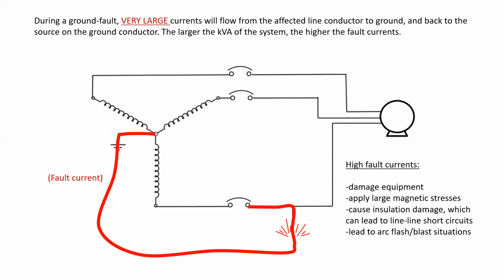And as systems get larger and larger, because we use more and more electricity, we tend to get more extreme situations. So with a solidly grounded system, we can get damaged equipment due to excessive magnetic stresses caused by the huge flow of current. We can have insulation damage, which can then lead to line-to-line short circuits. And we can also have significant arc flash situations, which can then result in personal injury.